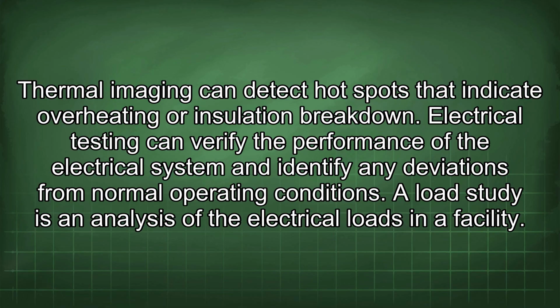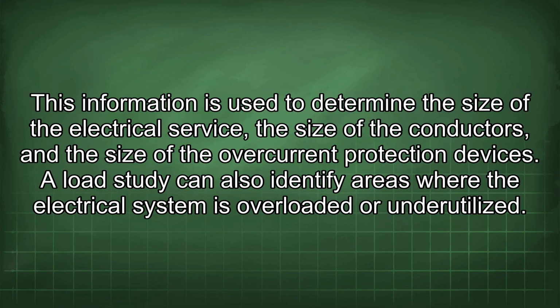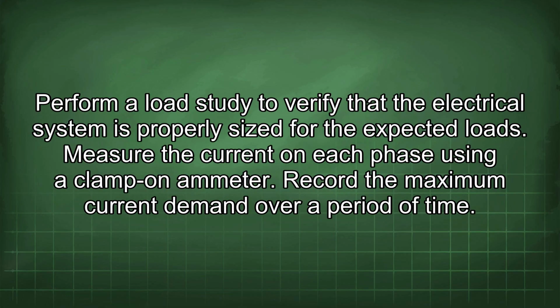A load study is an analysis of the electrical loads in a facility. This information is used to determine the size of the electrical service, the size of the conductors, and the size of the overcurrent protection devices. A load study can also identify areas where the electrical system is overloaded or underutilized. Perform a load study to verify that the electrical system is properly sized for the expected loads.